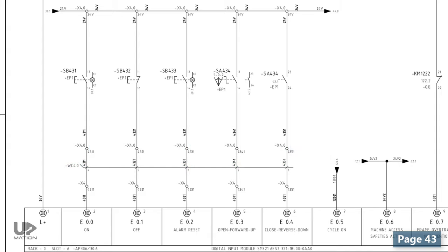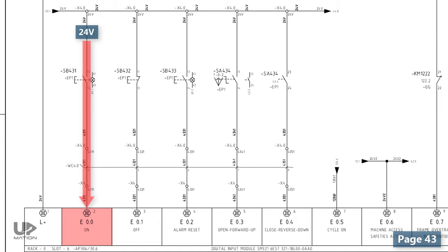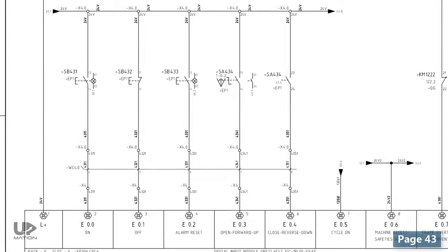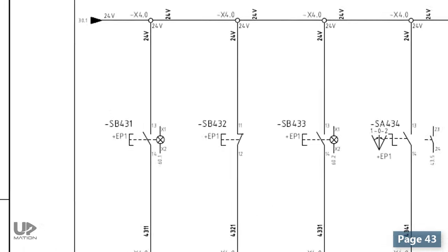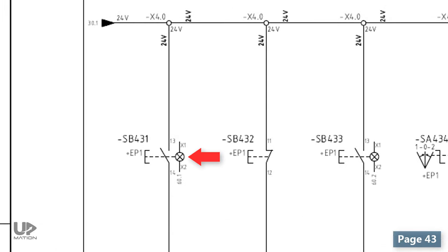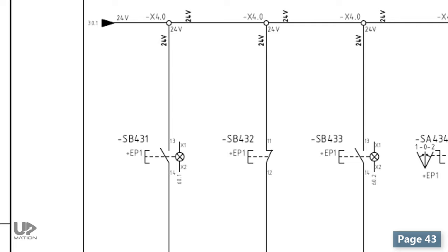Obviously, when we push this push button, the 24V signal will be transferred to the first channel of the first byte of this digital input card and will signal the PLC to turn on the device. This circle here shows that this is an illuminated push button and this is the sign for an indicator lamp. When this push button is pushed and the device turns on, therefore the PLC should send out a command from one of its digital output cards to turn on this indicator lamp.